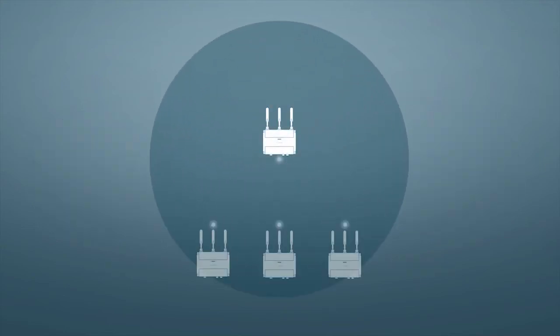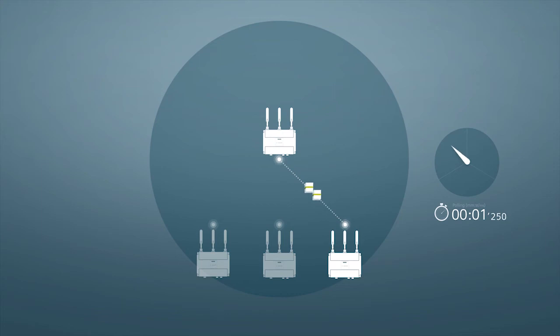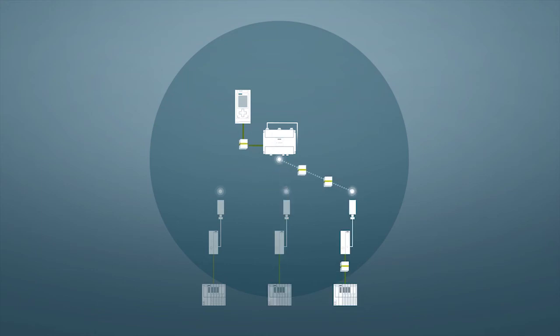The basic principle of IPCF is the cyclic polling of all clients through the access point. Each client has a reserved time window for data transmission. This also makes real-time communication via PROFINET possible. The data rate can be set flexibly or fixed, depending on the application.